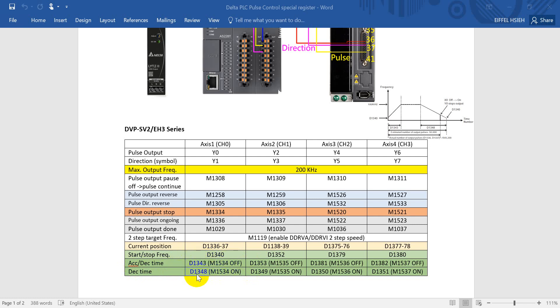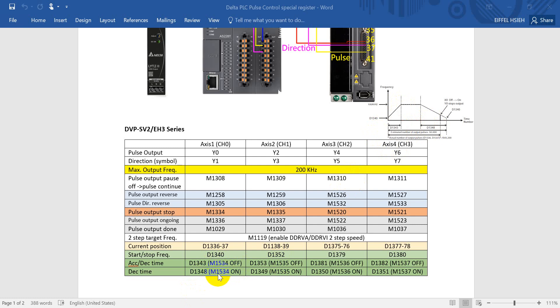So here I just want to remind you that we can separate or we can define in either the same data register or different data registers based on the status of this special flag. For example, channel 1, if M1534 is off, then that means both acceleration and deceleration will be D1343. But once we turn on M1534, then the acceleration will use D1343 and deceleration will use D1348.